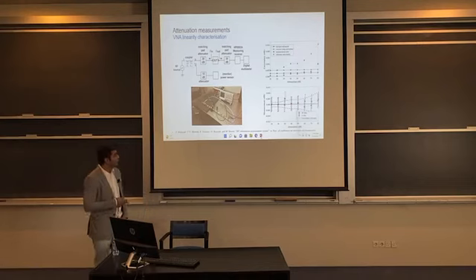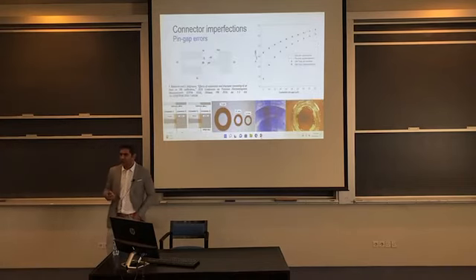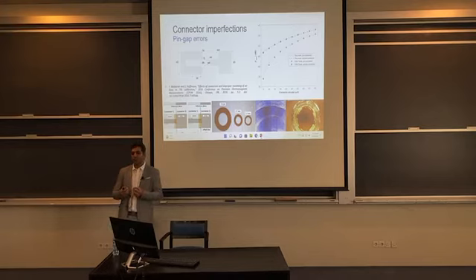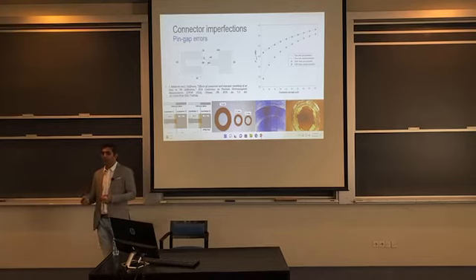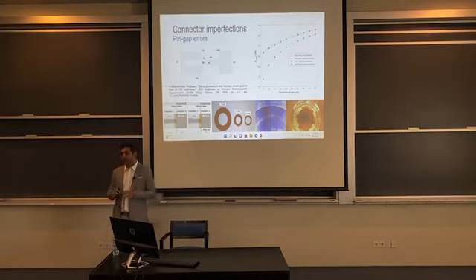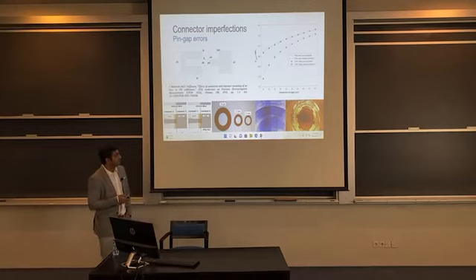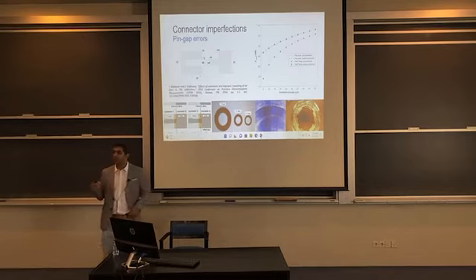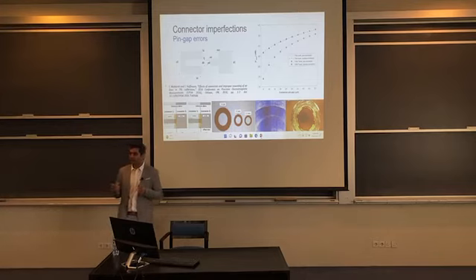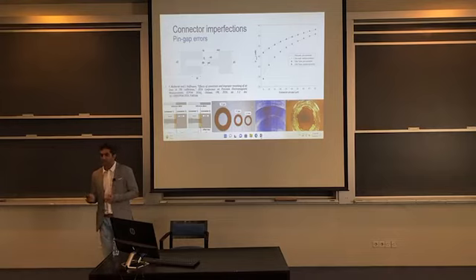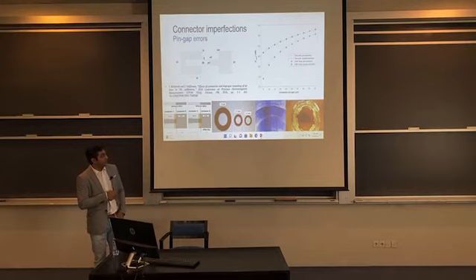Right? So these two setups are needed, but apart from that, if you want to estimate the accuracy of your measurement, you need to look at every element which is involved in that system. For example, RF cables. Regardless of whatever you build in high frequency measurements, you will be using cables. Accurate cables, and we buy some of the best cables that you can buy, but even those cables and connectors are actually imperfect. For example, these metrology grade connectors, as you can see, still have some mechanical tolerances. The manufacturers of these connectors still have tolerances due to which you will get some errors. So what we do is we actually characterize even these connectors.